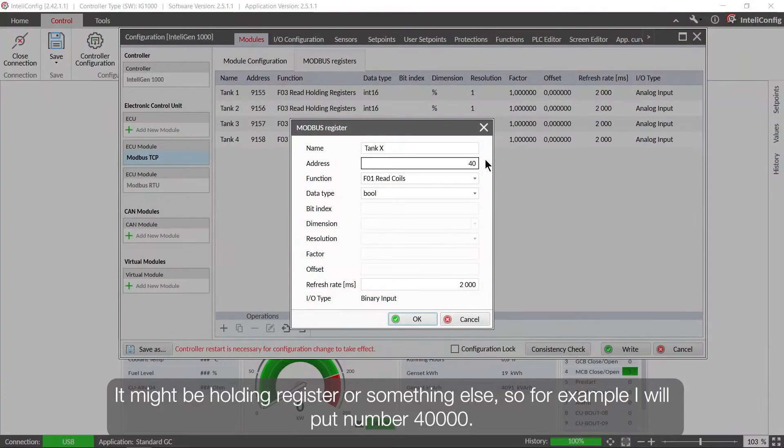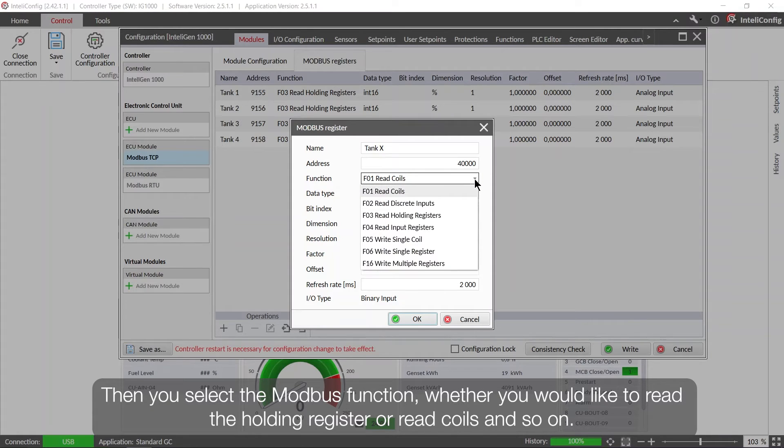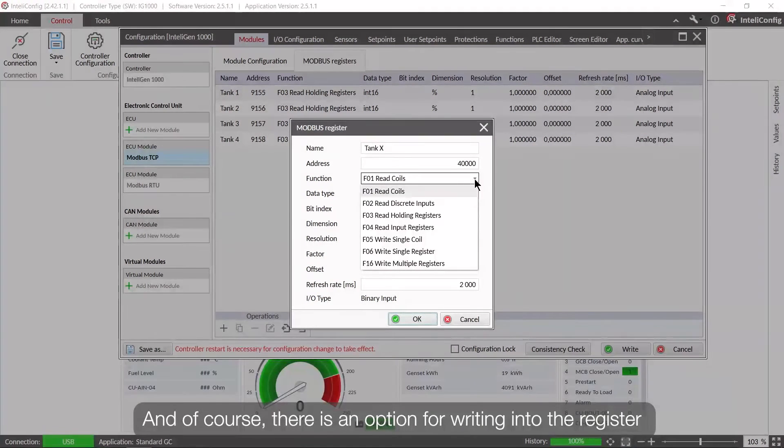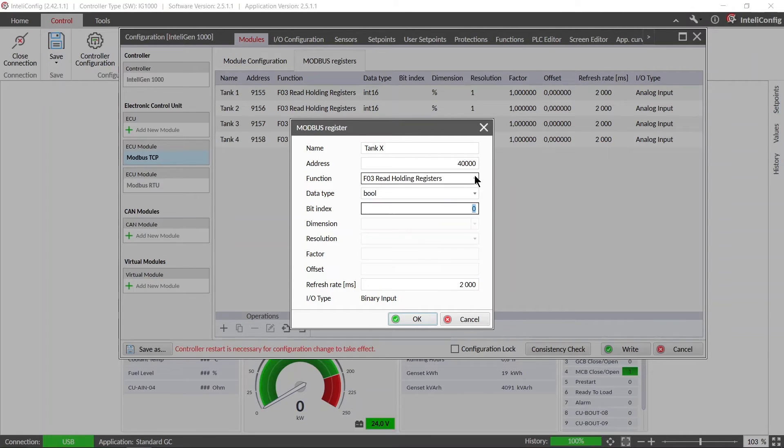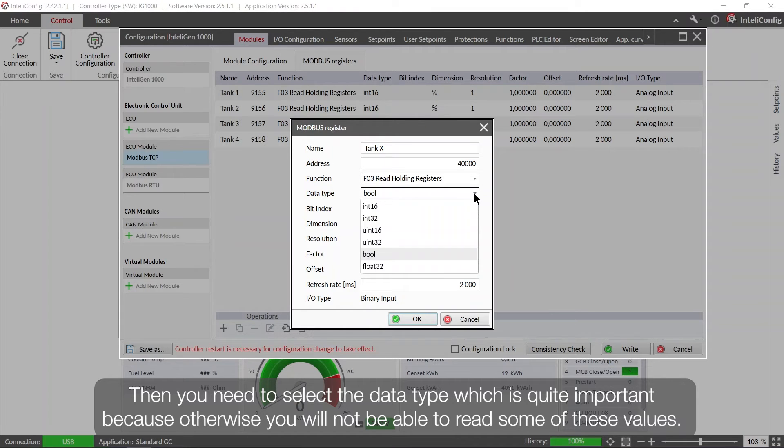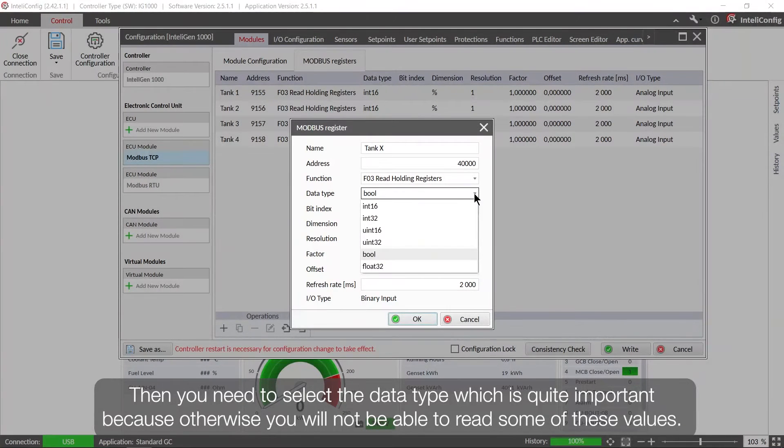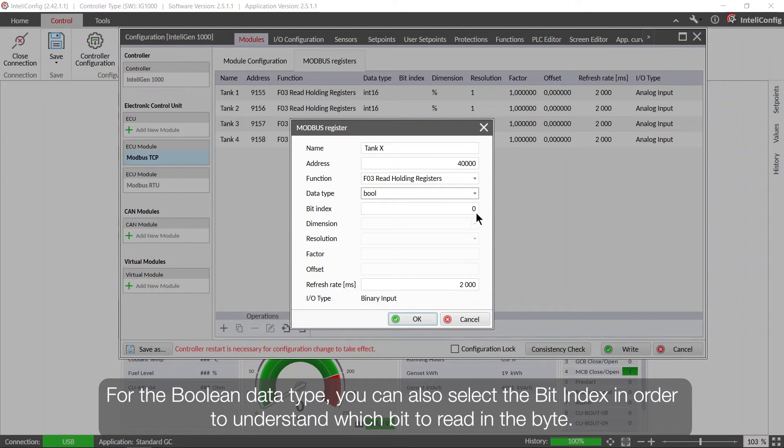So for example I will put number 40,000. Then you select the Modbus function whether you would like to read the holding register or read coils and so on, and of course there is an option for writing into the register since we are using the Modbus master functionality. Then you need to select the data type which is quite important because otherwise you will not be able to read some of these values. For the boolean data type you can also select the bit index in order to understand which bit to read in the byte.